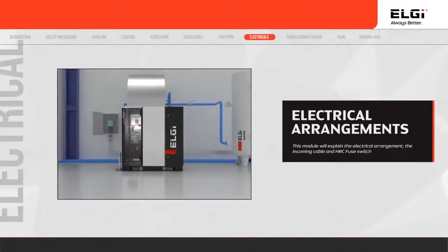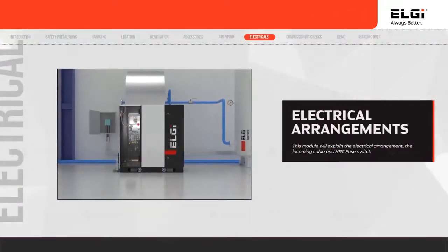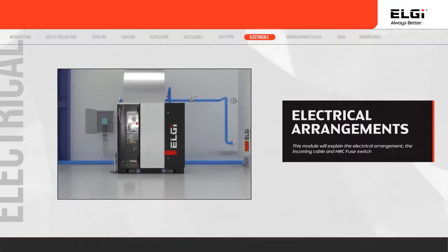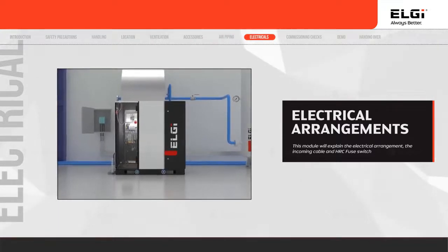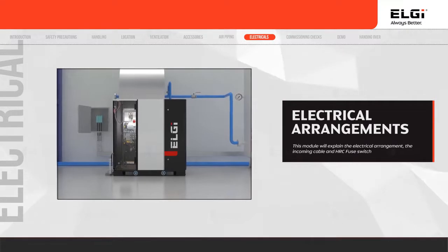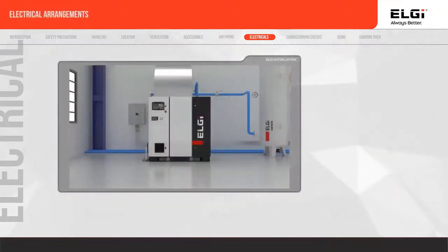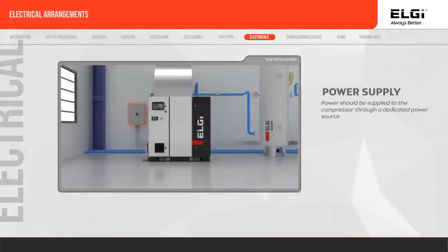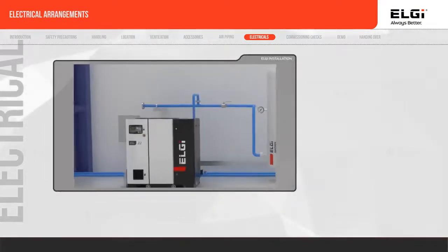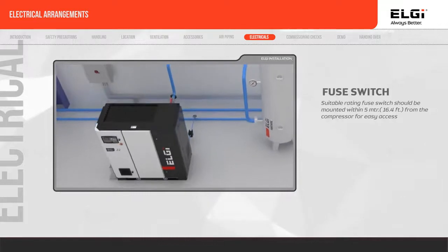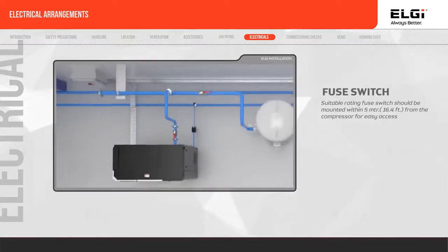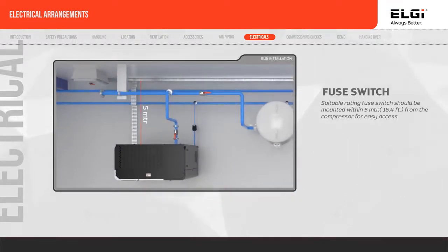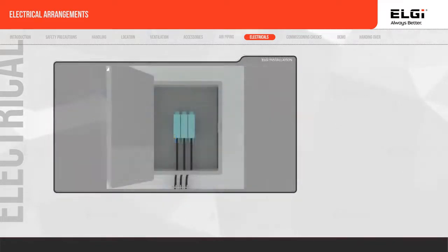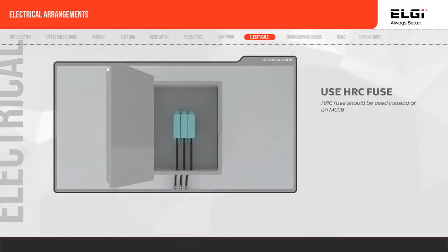Electrical connections with the right electrical components is very important. This section explains the electrical arrangement about the cable and the HRC fuse switch. Power should be supplied to the compressor through a dedicated power source. Suitable rating fuse switch mounted within 5 meters, 16.4 feet, from the compressor for easy access. Use a HRC fuse instead of an MCCB.